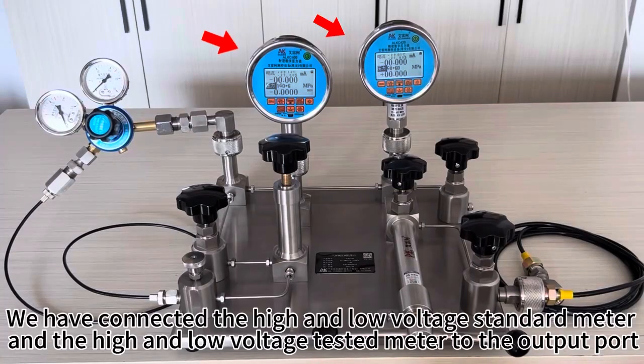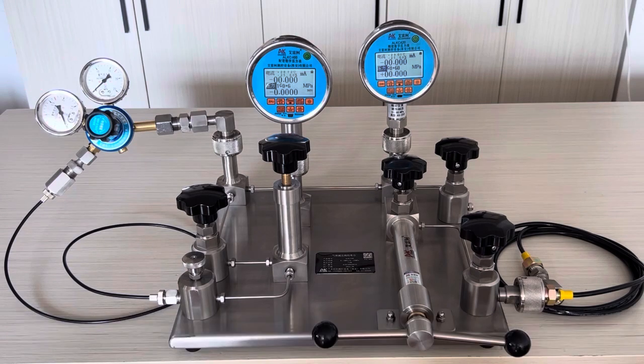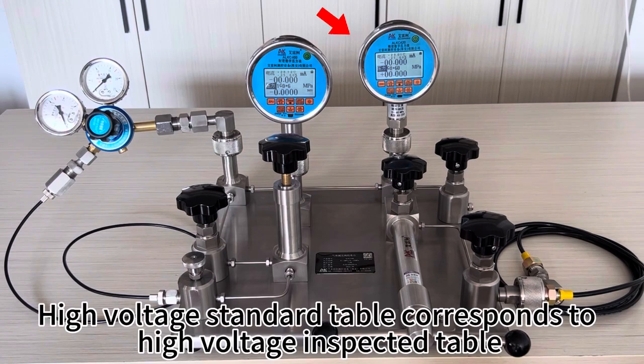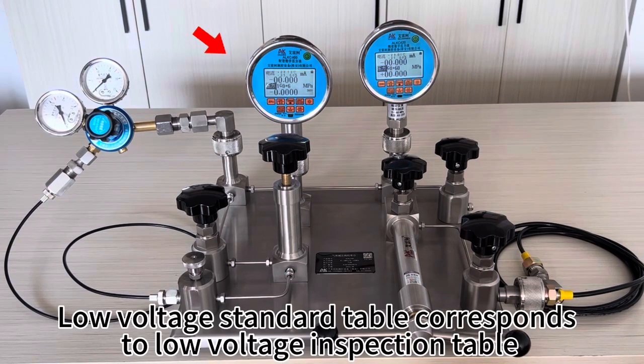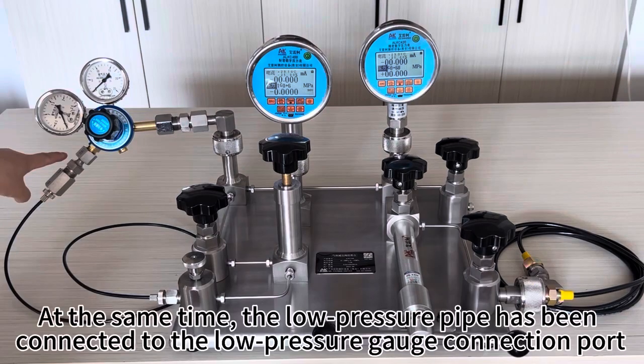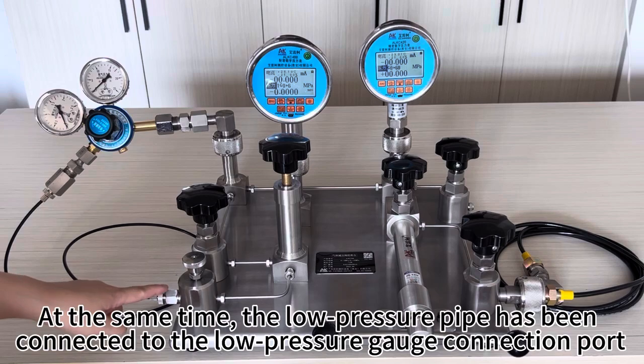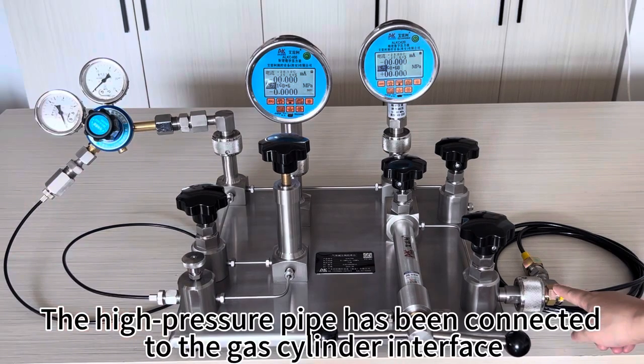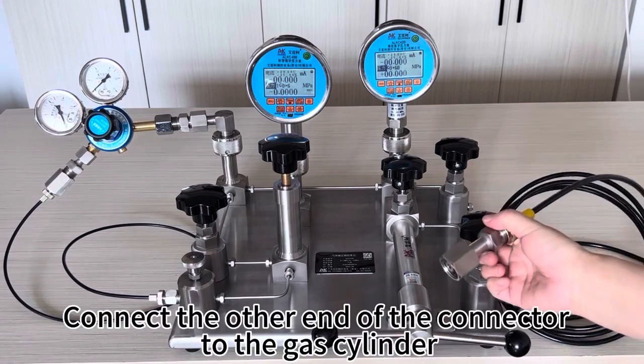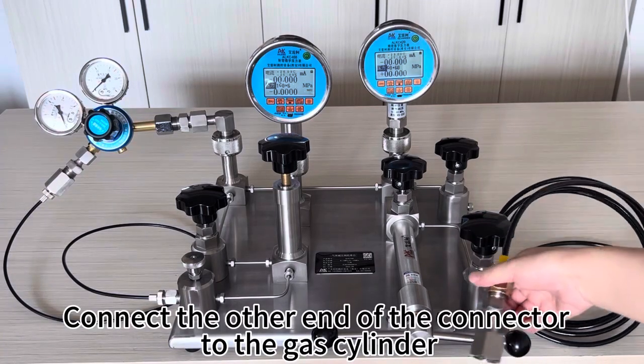We have connected the high and low-pressure standard meter and the high and low-pressure tested meter to the output port. High-pressure standard table corresponds to high-pressure inspected table. Low-pressure standard table corresponds to low-pressure inspection table. At the same time, the low-pressure pipe has been connected to the low-pressure gauge connection port. The high-pressure pipe has been connected to the gas cylinder interface. Connect the other end of the connector to the gas cylinder.